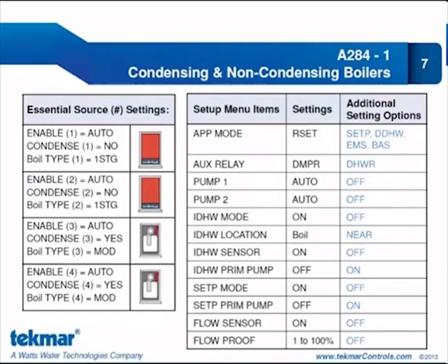If we are doing set point, we turn that mode to on and specify whether the primary pump needs to operate. Our set point load is also piped in parallel, so we turn primary pump off. We do have a flow sensor connected, so we turn flow sensor on. Because we are using that flow sensor to provide proof of flow, we must also select a flow proof percentage — the percentage of full flow that must be achieved to provide proof. If you are using the flow sensor for measurement purposes only and not to provide proof, you would select off.